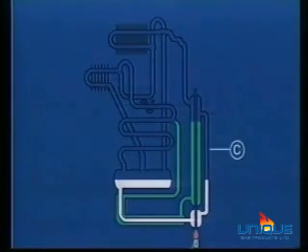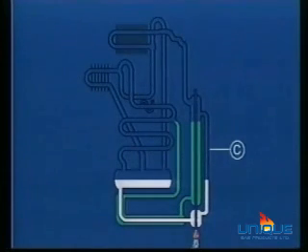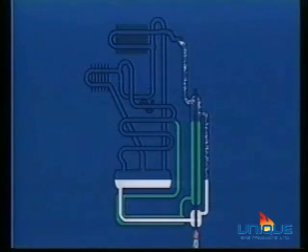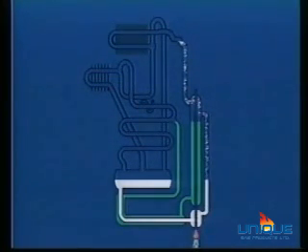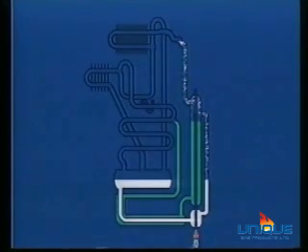When entering pipe C, this water and ammonia solution evaporates and rises up to the condenser. However, the water cannot reach the condenser as its boiling point differs from the ammonia's. It is then condensed and returns to the absorber through pipe B. This is called a poor solution.